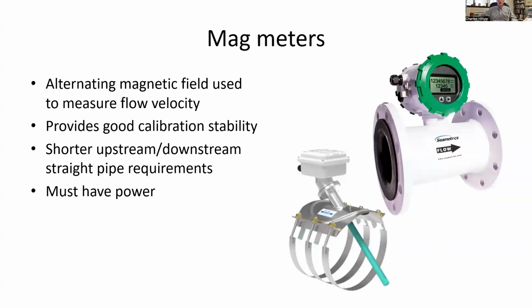Now, the meter that's become very popular over the past several years is the mag meter. The mag meter basically uses an alternating magnetic field to measure the flow velocity. It's nice because it doesn't have any moving parts. It has very low head loss, and it can be installed either as a flanged inline device or as a saddle mount. They have very good calibration stability, so their calibration lasts a long time, and they have shorter upstream and downstream straight pipe requirements. However, these devices must have power to operate, so if your battery goes dead, you're losing data.